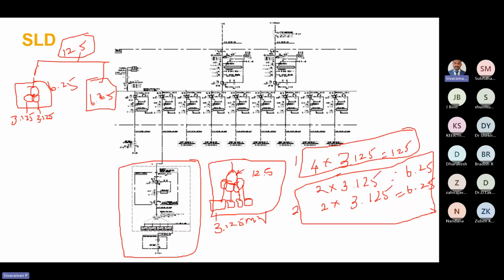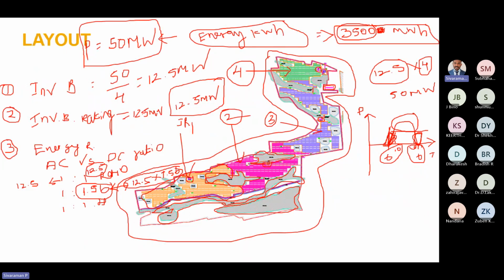As I told, we have to maintain an energy of 3500 megawatt hour at the interconnection point, minimum. By considering the losses, what are the losses in the plant? One is the DC loss, then the AC loss. In the DC loss, what losses will come? The DC cable, and the inverter will also have some losses. On the AC side, what losses will come? The inverter duty transformer, where losses will also be there, and the AC cables.